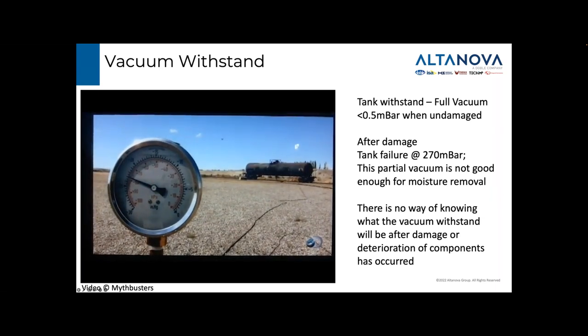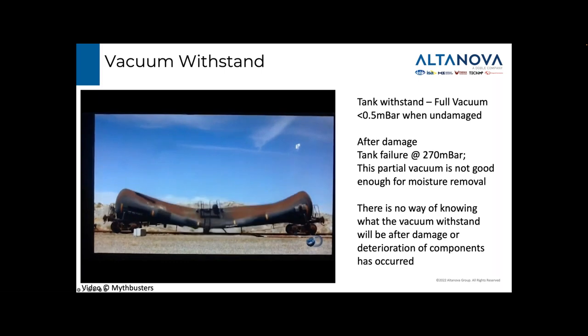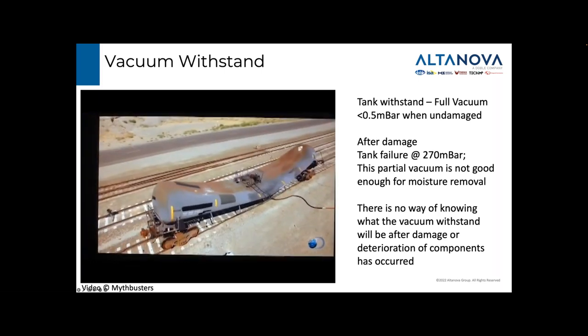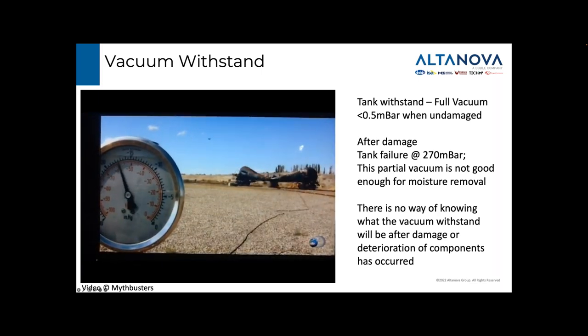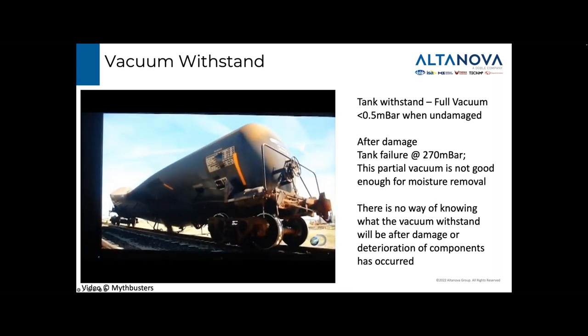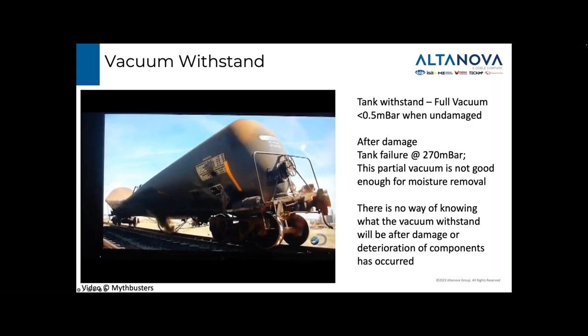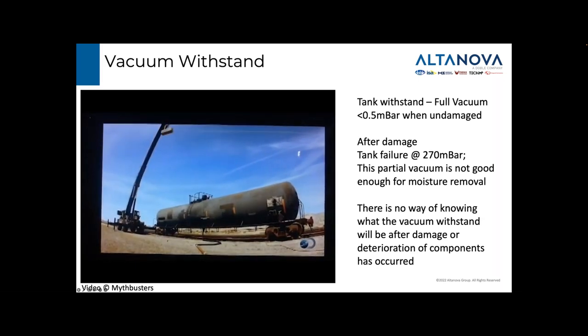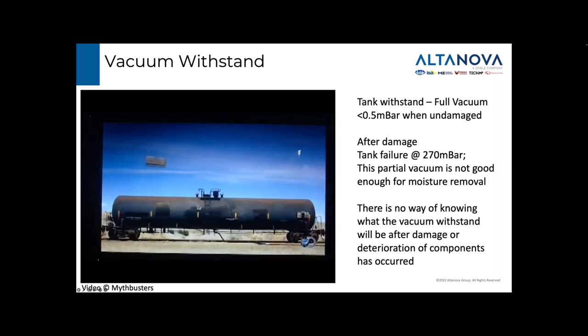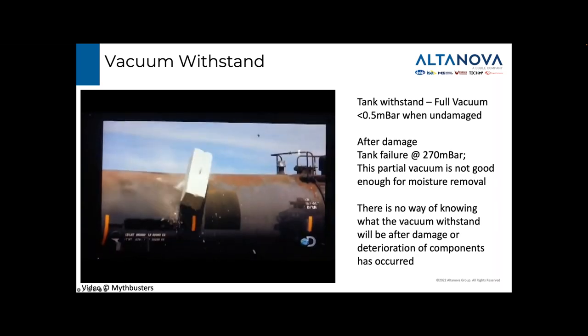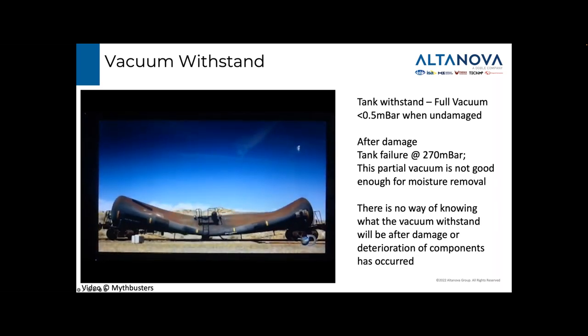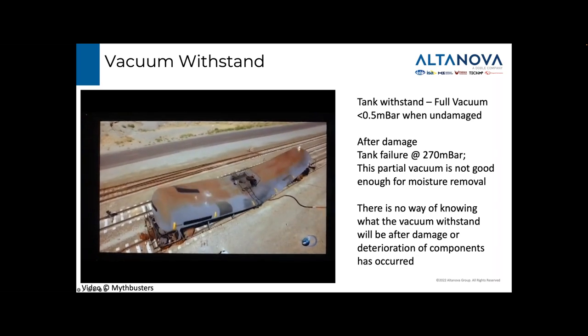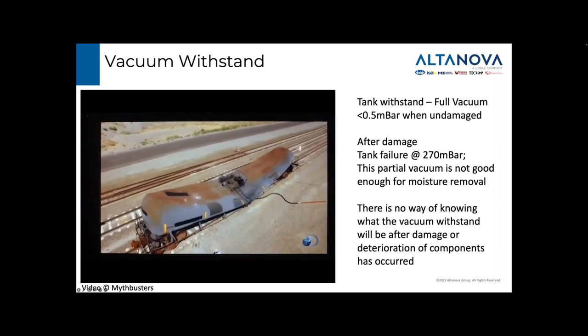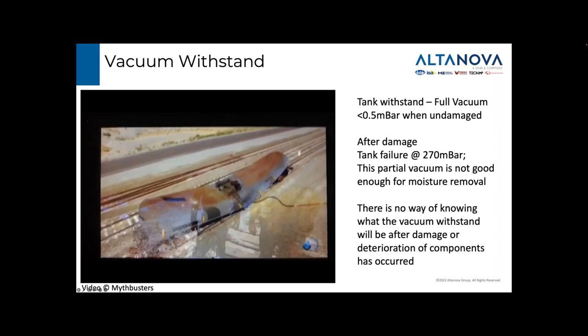Here is a short video from MythBusters. They were demonstrating how a tank defect could affect the vacuum withstand of a container. Okay, so this isn't a transformer, but the principle is the same. The tank was first checked under full vacuum and found to withstand it. Then a defect was created and vacuum pulled again. This time the tank failed catastrophically at only 270 millibar. That's 500 times less than the 0.5 millibar achieved under normal full vacuum conditions. Imagine the risk of collateral damage to equipment or personnel if this happened during your maintenance.